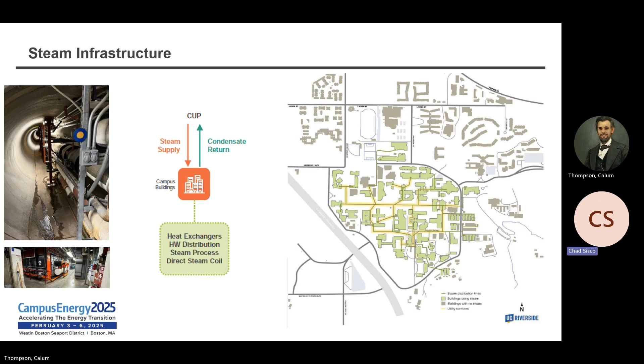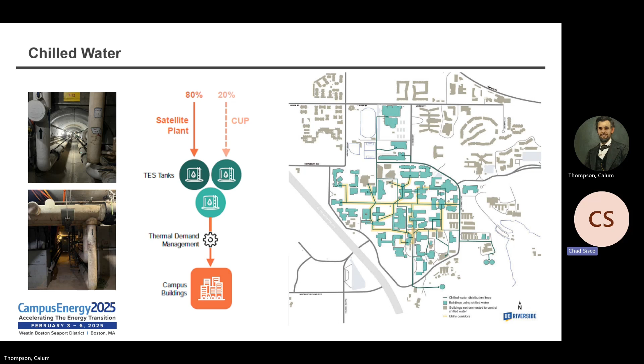For our chilled water, we have two chilled water production plants: one central plant and one satellite plant. Our satellite plant is the newest, built in 2002, and it does 80% of our chilled water production. Our central plant does the other 20%. We've been using TES for quite some time now, and it's helped a lot with our load reduction and demand reduction during on-peak times. During our analysis, we found that this is going to help us dramatically when we incorporate new technologies such as heat recovery chillers and heat pump chillers.